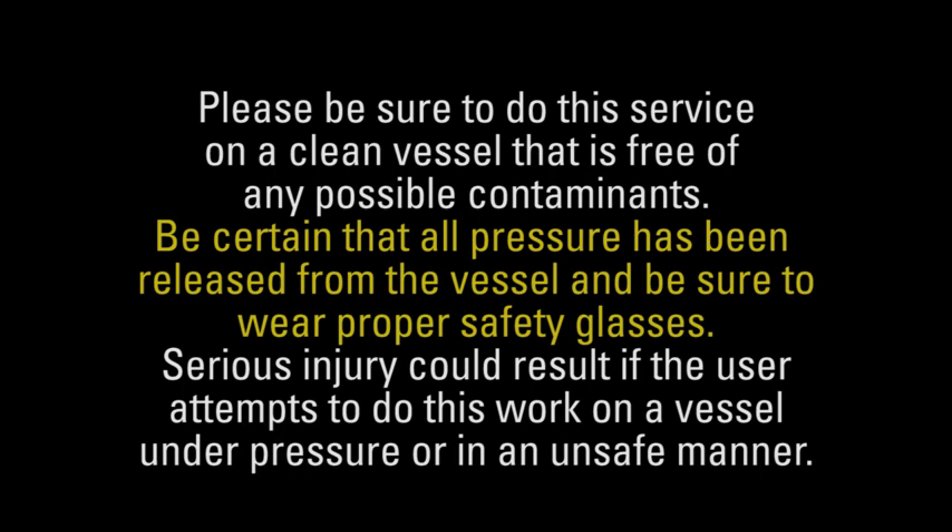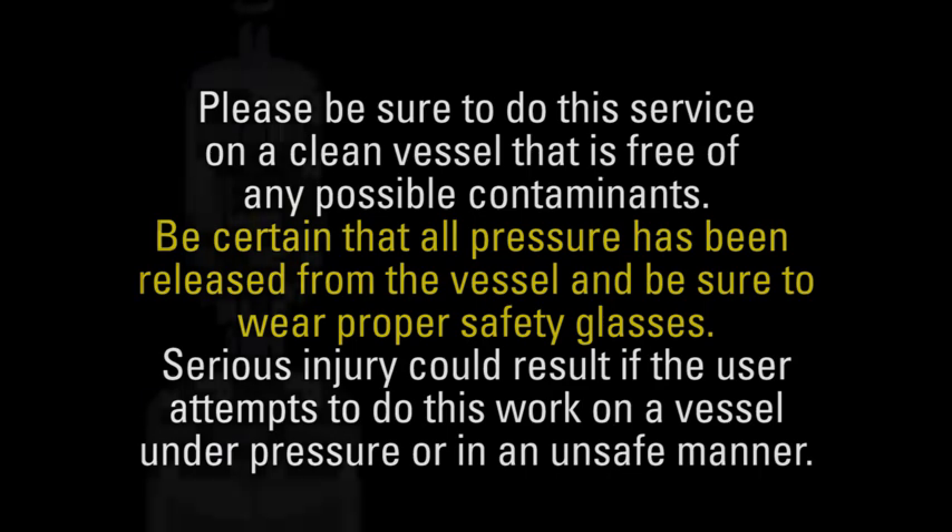This video will cover the rebuilding of the consumable parts in a Parr Magnetic Drive. Please be sure to do this service on a clean vessel that is free of any possible contaminants. Be certain that all pressure has been released from the vessel and be sure to wear proper safety glasses. Serious injury could result if the user attempts to do this work on a vessel under pressure or in an unsafe manner.